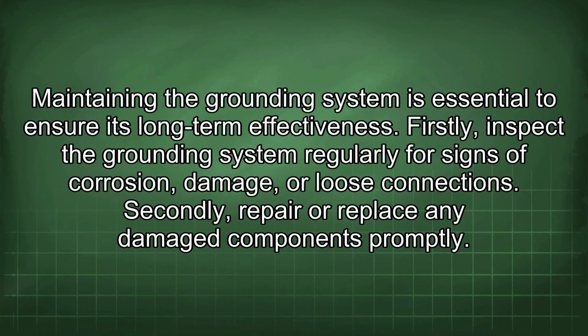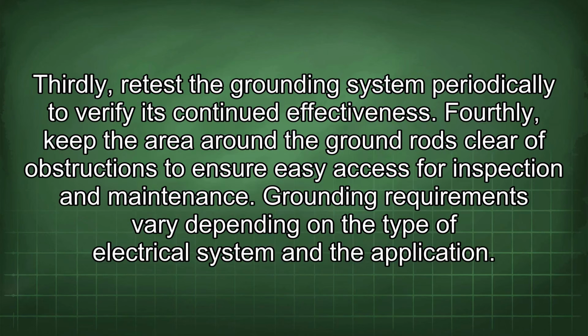Maintaining the grounding system is essential to ensure its long-term effectiveness. Firstly, inspect the grounding system regularly for signs of corrosion, damage, or loose connections. Secondly, repair or replace any damaged components promptly. Thirdly, retest the grounding system periodically to verify its continued effectiveness. Fourthly, keep the area around the ground rods clear of obstructions to ensure easy access for inspection and maintenance.